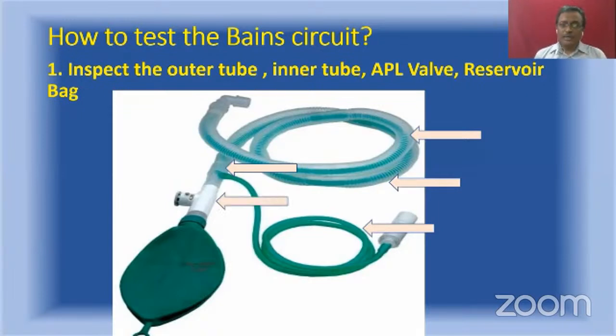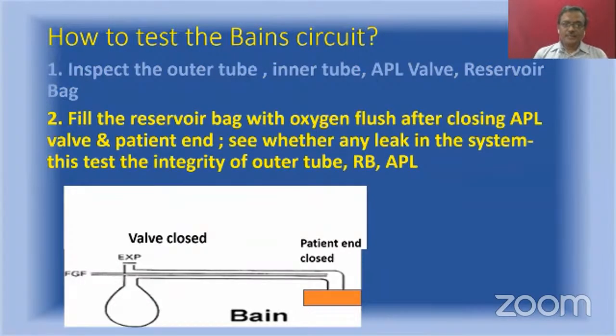You look at the APL valve. You check that the APL valve is moving freely or not. And you look at the reservoir bag. This is simple inspection. Now next, you are going to check whether there is any leak in the system.